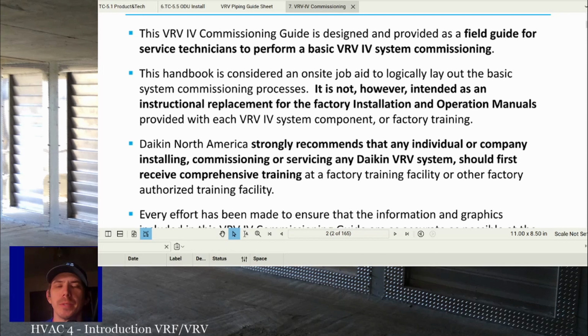So it's extremely important when it comes to these systems that you do everything the way it's supposed to be, exactly by the book, no cutting corners, because you do not want to be responsible for any malfunctions in equipment operation. They say that 95% of all equipment failures are installation error in one form or another. That may or may not be a little bit of an overstatement, but it generally does hold true. And again, when you're talking about a large, complex commercial system, you do not want to be the one who made critical errors in the installation or commissioning of that equipment. So, those are your two big rules you should remember right off the bat. You want to follow manufacturer's instructions and you want factory quality work every time.